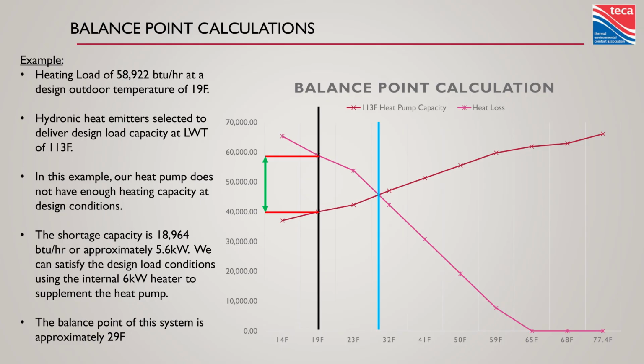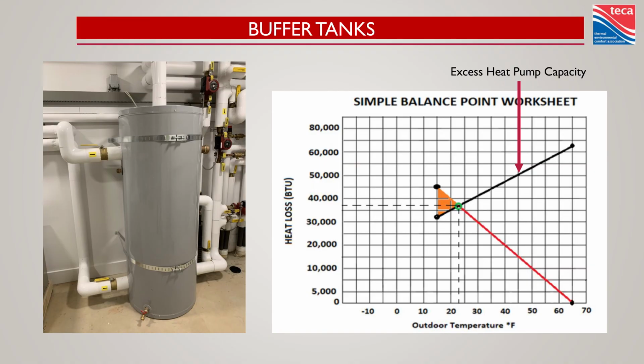Right here on this 59-degree day, look at how much heat my heat pump wants to give me, and look at what the house can take if every single zone is open. That's why we need buffer tanks in these systems, to prevent short cycling. We've got formulas to size them based on temperature difference in the tank, based on minimum zone load. Happy to go through all that in detail at a time when I've been given more time. But nonetheless, they look like this.